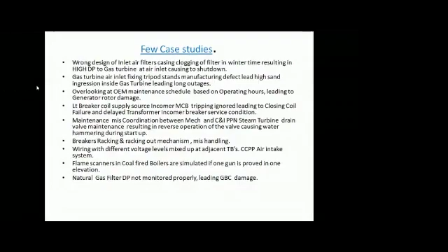And also, for example, in most coal-fired power plants, in one elevation, if one gun is proved, then they simulate the other guns so that the total elevation is proved. Normally people do this to save time, because otherwise they have to shut down, then clean and do all those things. Or they say one elevation is okay, so both cross-functional elevations are proved sufficient. Like that, people do some simulations, which again is not correct.